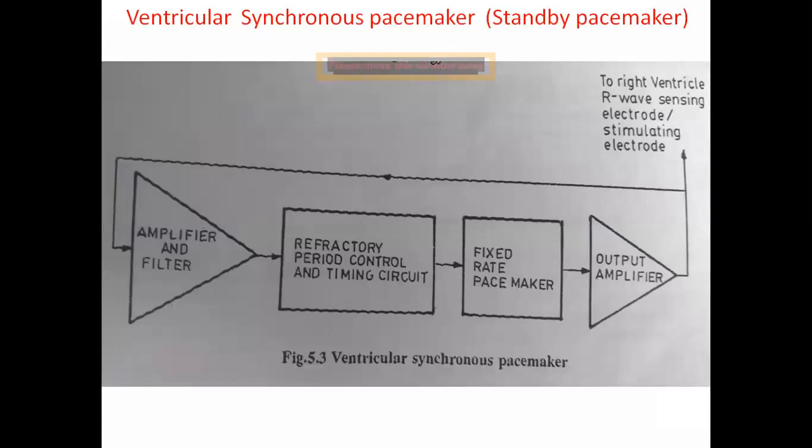Coming to the next one, the ventricular synchronous pacemaker. We can call it a standby pacemaker, or an R-wave triggered pacemaker, because it senses the generated R-wave signal, and based upon that it acts and produces the output signal, and that output signal is applied again to the heart.